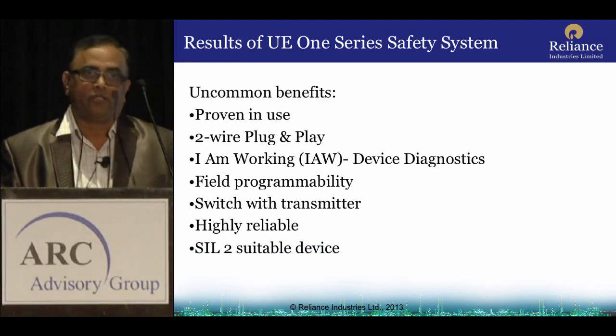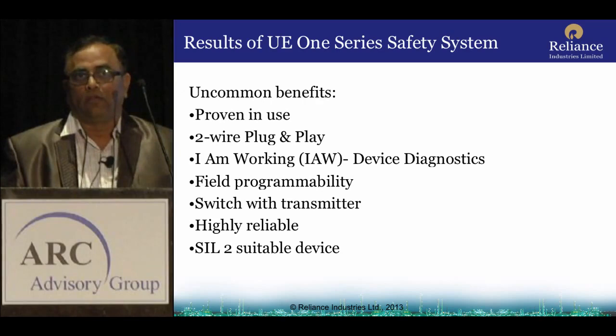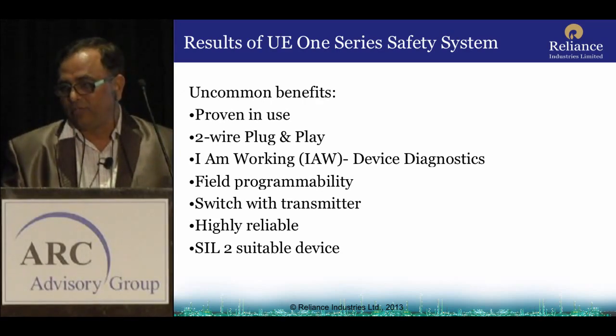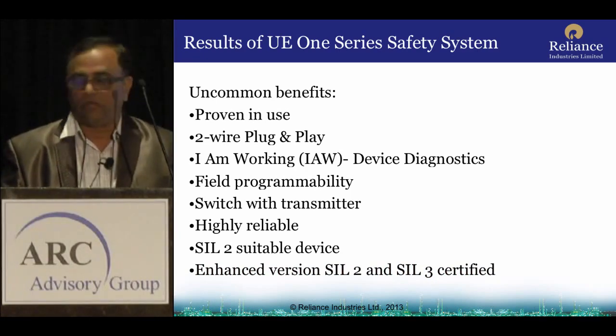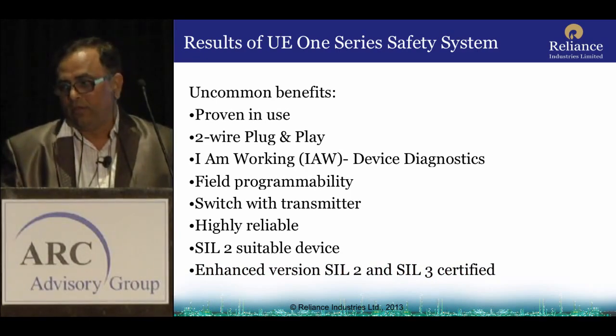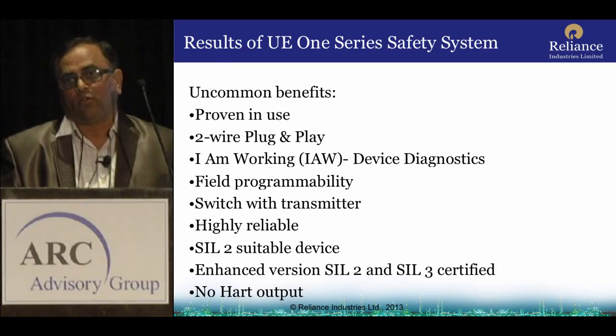It is a SIL 2 suitable device; they have now come out with the certification, and the enhanced version is certified for SIL 2 and SIL 3 also. There is no HART output, that is what it is.